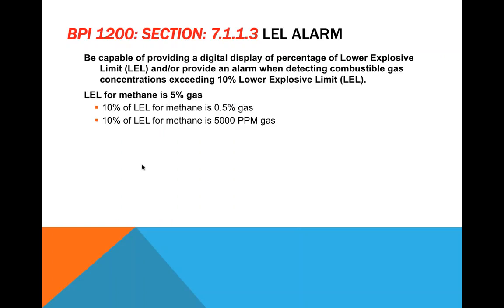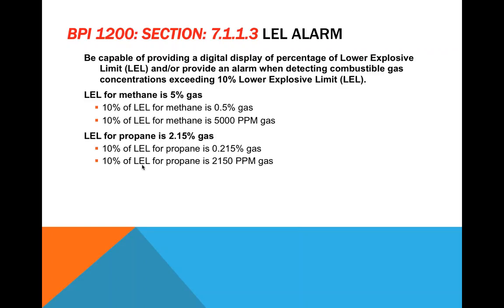And again, the LEL for methane, as we talked about before, and propane are two different levels, at small concentrations of gas. You do need a precision sensor to measure this. So basically, if there's no LEL display or alarm at 10% LEL, it's a no-go for BPI 1200. Any device that does not provide an LEL display or LEL alarm is a no-go for the BPI 1200 standard.